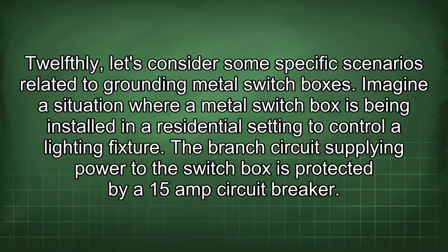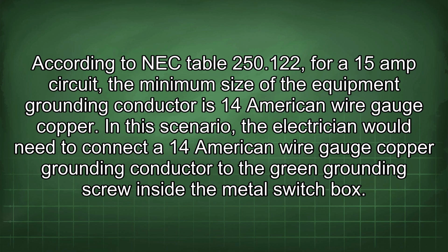12thly, let's consider some specific scenarios related to grounding metal switch boxes. Imagine a situation where a metal switch box is being installed in a residential setting to control a lighting fixture. The branch circuit supplying power to the switch box is protected by a 15 amp circuit breaker. According to NEC table 250.122, for a 15 amp circuit, the minimum size of the equipment grounding conductor is 14 American wire gauge copper.